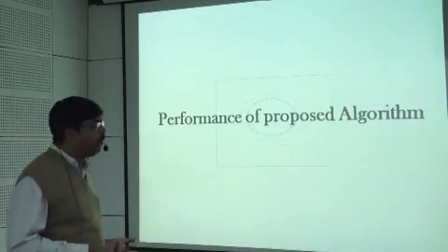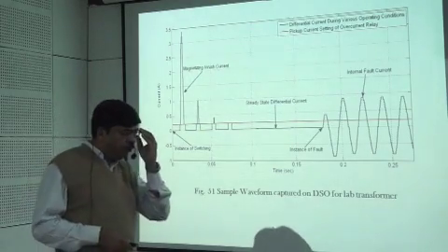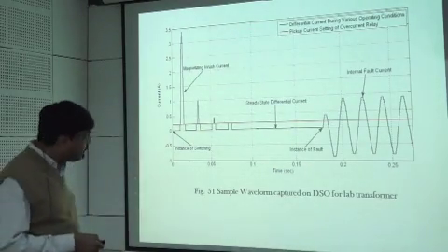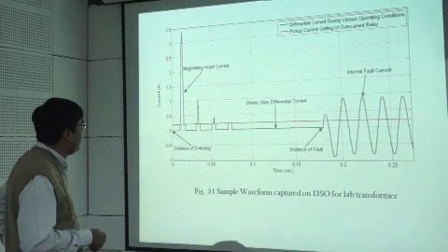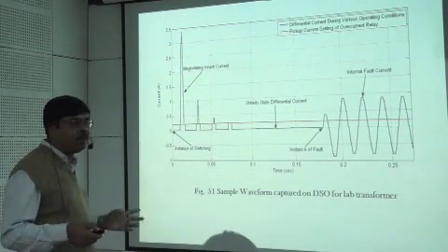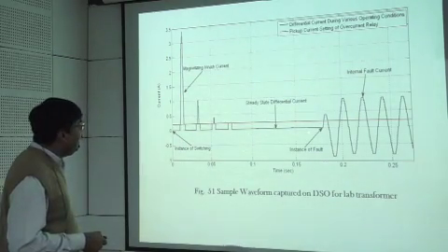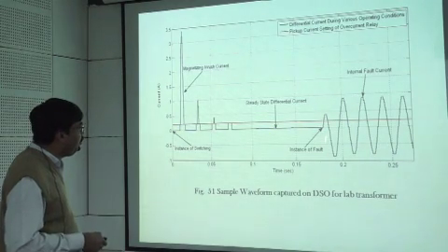Performance of the proposed algorithm. This is a sample waveform captured on a laboratory DSO. This is an instance of switching. We have an inrush current. Then it dies out depending upon the time constant. And then at this instance I have performed a fault.